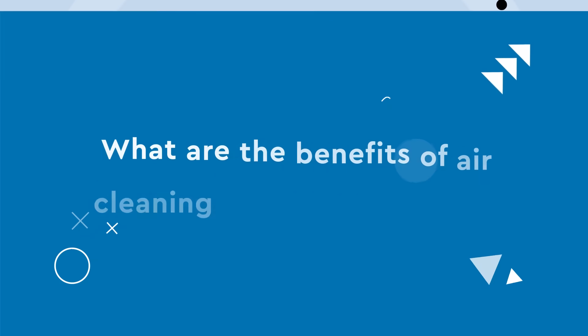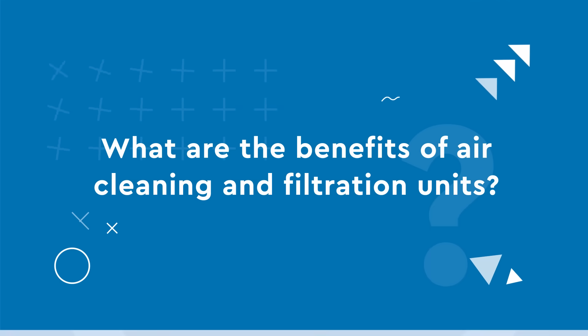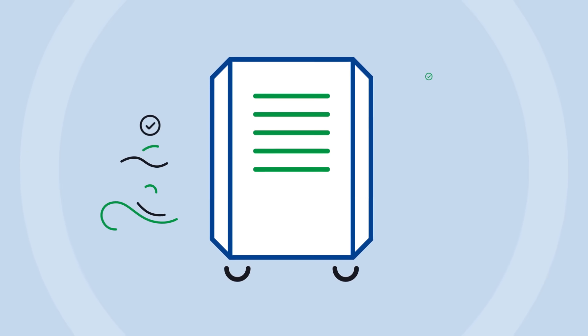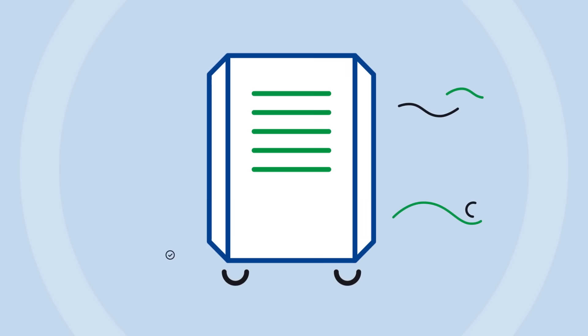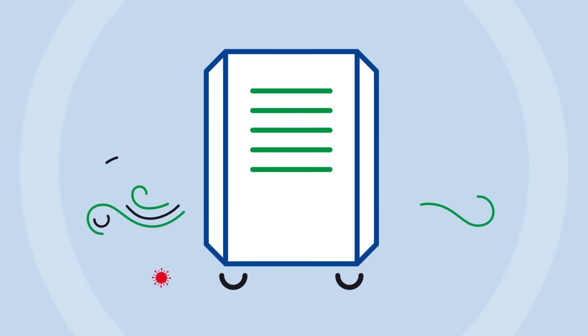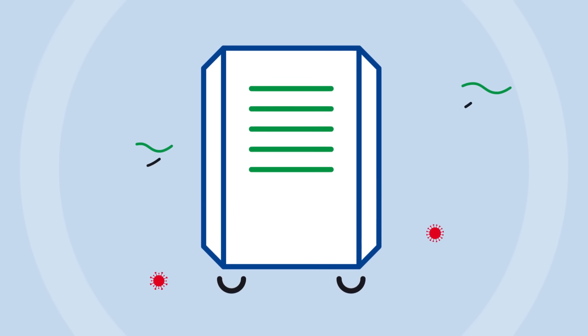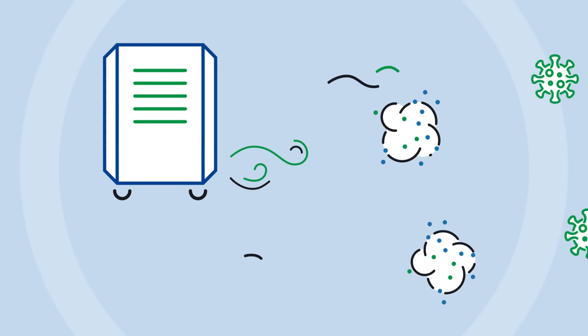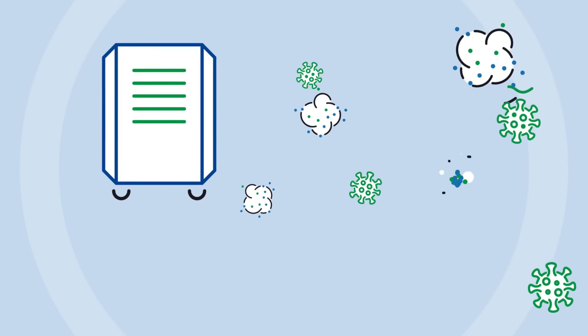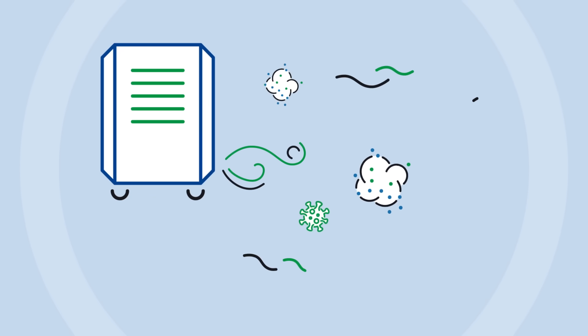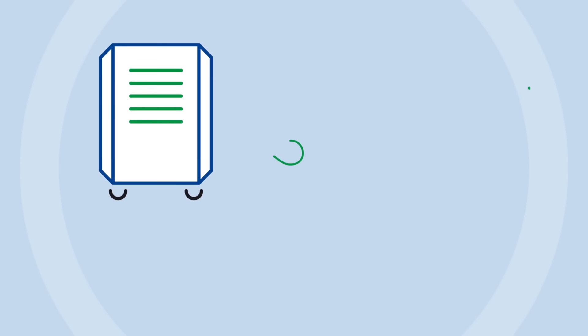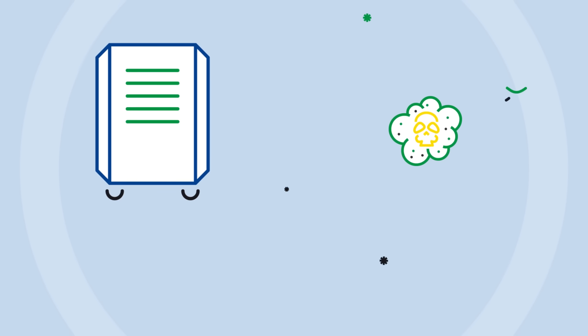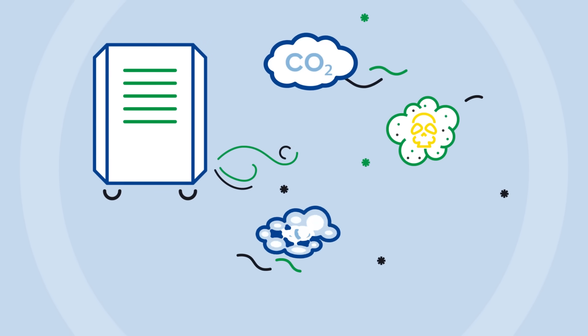What are the benefits of air cleaning and filtration units? You can use local air cleaning and filtration units to improve air quality, but you must be aware these devices have limited capabilities. The majority are based on particulate filtering and will only reduce dust levels and bio-aerosols. Very few of these devices can reduce levels of formaldehyde, VOCs, and carbon dioxide.